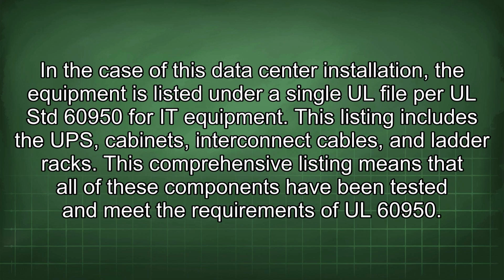In the case of this data center installation, the equipment is listed under a single UL file per UL STD 60950 for IT equipment. This listing includes the UPS, cabinets, interconnect cables, and ladder racks. This comprehensive listing means that all of these components have been tested and meet the requirements of UL 60950.